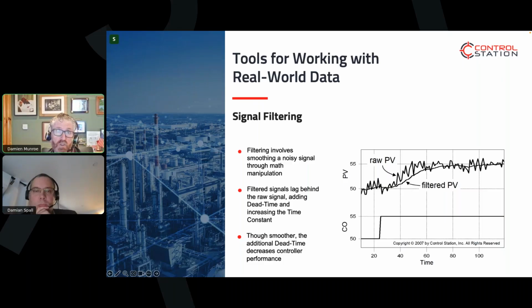We have perceived that the process is running much slower than what it is in reality. If we tune to that filtered value, the system will get away from us. The system will start to respond much more aggressively to our reaction to it. Dead time, remember, is from the instant the output changed till the PV started moving in the upward direction.